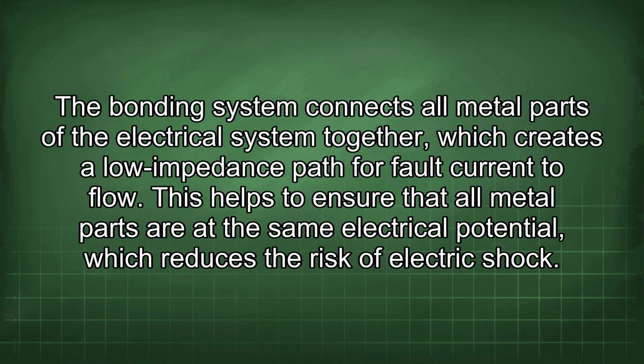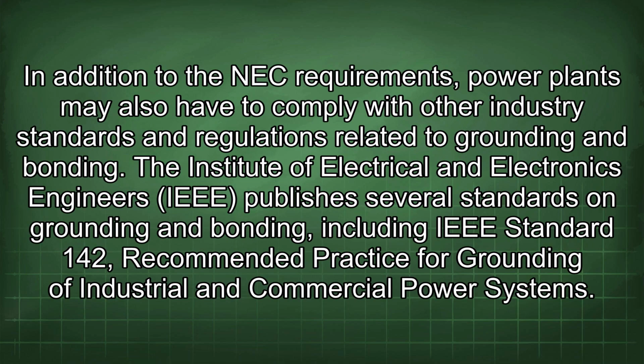The bonding system connects all metal parts of the electrical system together, which creates a low impedance path for fault current to flow. This helps to ensure that all metal parts are at the same electrical potential, which reduces the risk of electric shock. In addition to the NEC requirements, power plants may also have to comply with other industry standards and regulations related to grounding and bonding.